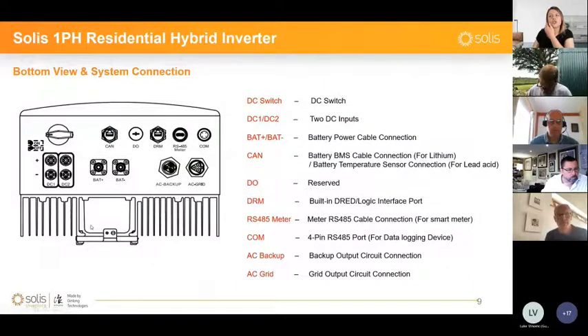I will show you a little bit on the bottom view and the system connections. All of our inverters that we're selling on the UK market currently all include a DC switch. So in theory, you won't need an external DC switch unless the regulation asks for it. As I mentioned, there are 2 DC inputs, so this DC switch is going to cut off the input on both DC inputs.